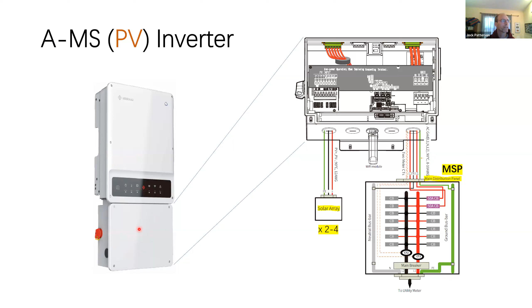When you're placing the inverter, it's fairly standard. We obviously have to pay attention to the environment. So while you don't have to keep it away from the sun, you want to keep it away from the sun, right? It's just an electronics good thing to do. You don't have to keep it out of the rain, but you want to, right? So especially if it's going to be in the rain, while it's NEMA 4X, it isn't once you take out the gaskets, or the rubber enclosures around the pre-drilled knockouts. Once you take those out, you now have to put in appropriate and well done rain tight fittings to return it to a NEMA 4X type inverter.